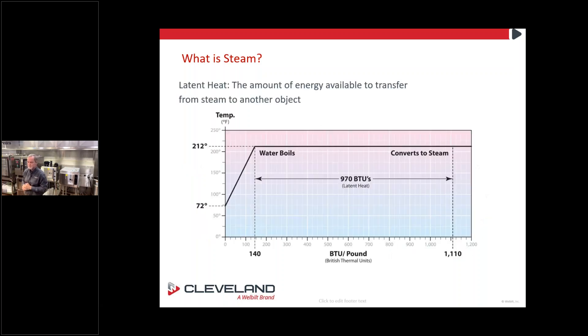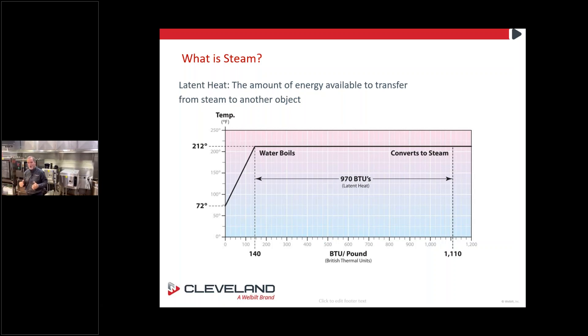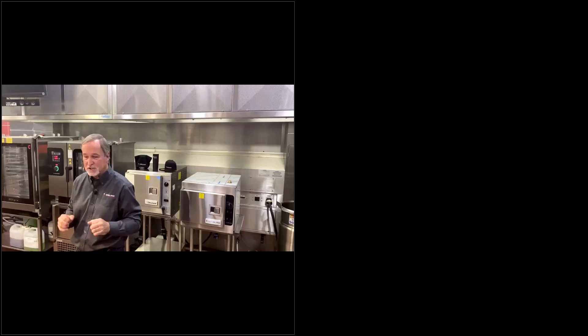From room temperature — 72 degrees — to a boil takes 140 BTUs of energy. However, to change state from water into steam takes another 970 BTUs of energy. So steam now has over a thousand BTUs of energy in it. That gives you an idea of how much energy steam carries.